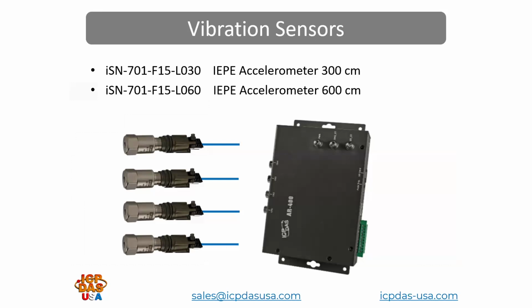We also make IEPE, standing for Integral Electronics Piezoelectric Accelerometers. They are also used as vibration sensors. The IEPE Integral Electronic Piezoelectric Accelerometers are powered by a constant current, typically 2 milliamps to 20 milliamps. The output signal from the accelerometer is a voltage signal that is superimposed onto the same line on which the constant current is supplied. Coaxial cable is typically used between an accelerometer and signal conditioner or data acquisition system.